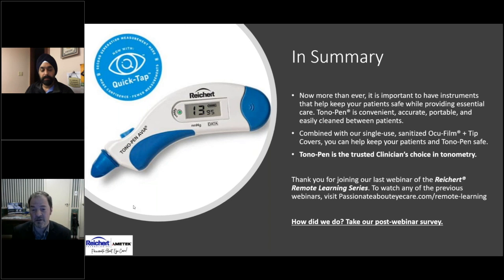Because all these devices are designed to read like a Goldmann on average, and they all have to pass FDA, right? So they shouldn't be dramatically off from each other. Of course, there are things like corneal thickness that can affect some devices more than others, and of course the Ocular Response Analyzer takes care of that. Tono-Pen does a good job with corneal centration, but all these things make it to the market, so they shouldn't be wildly off from one another. So if you have a tonometer that is consistently understating one of your other tonometers, or reading highly variable compared to one of your other tonometers, contact the manufacturer. If it's us, we would love to talk to you, and we'll get to the bottom of it.